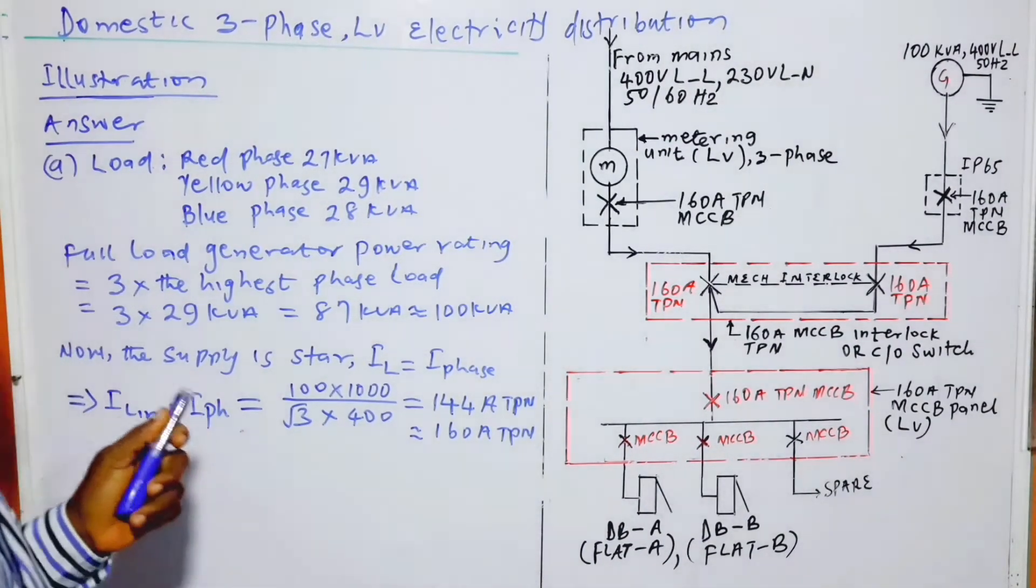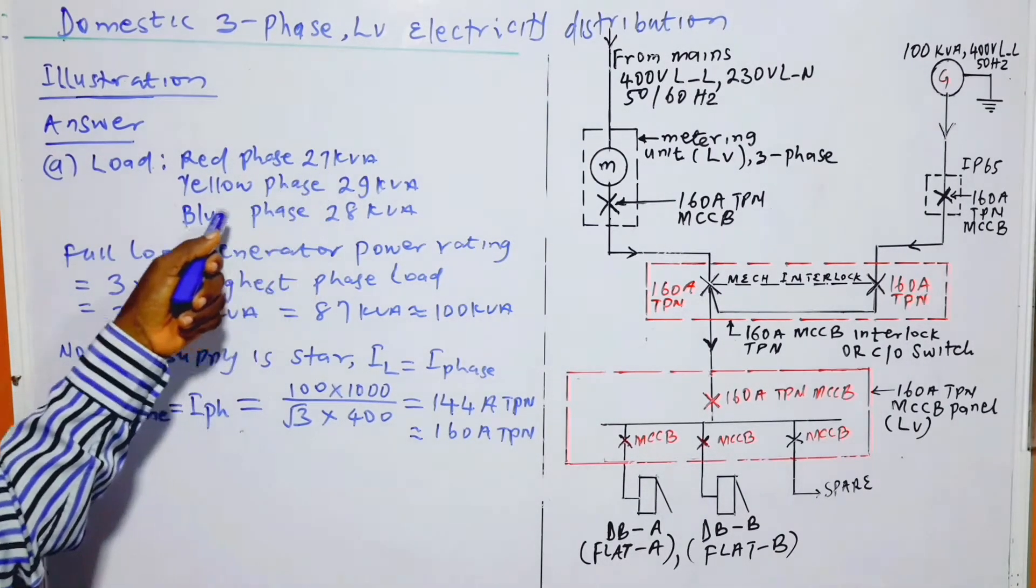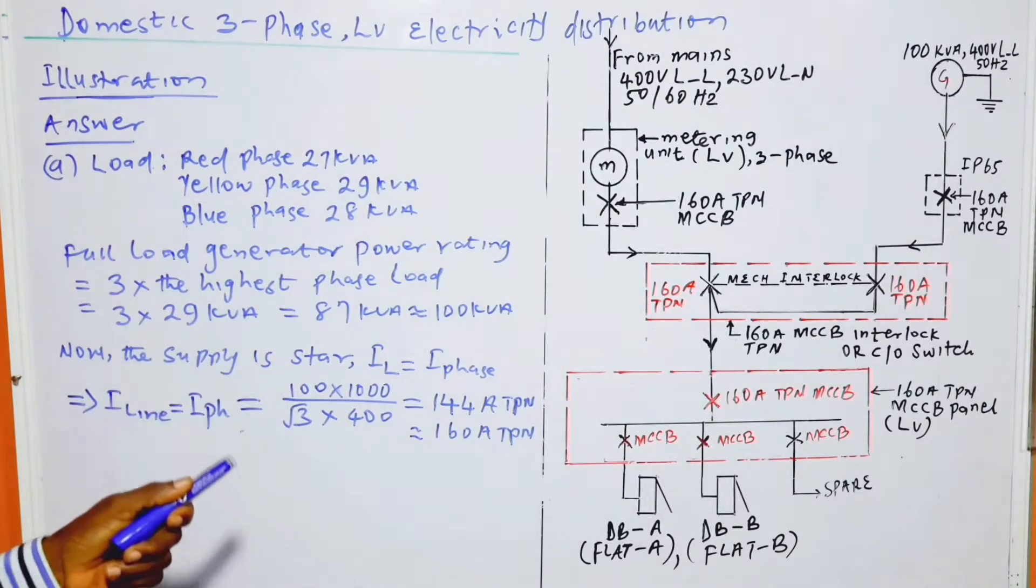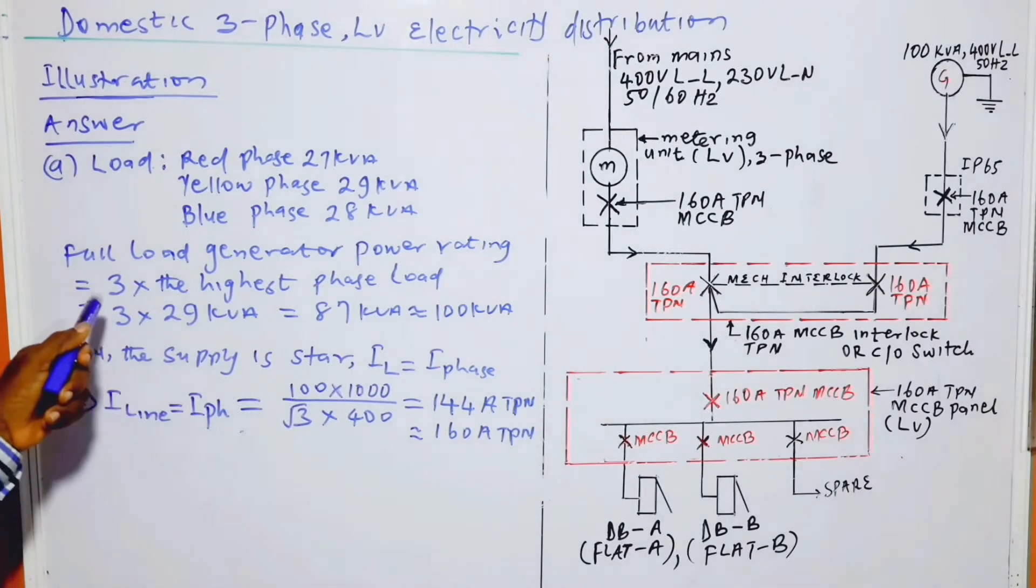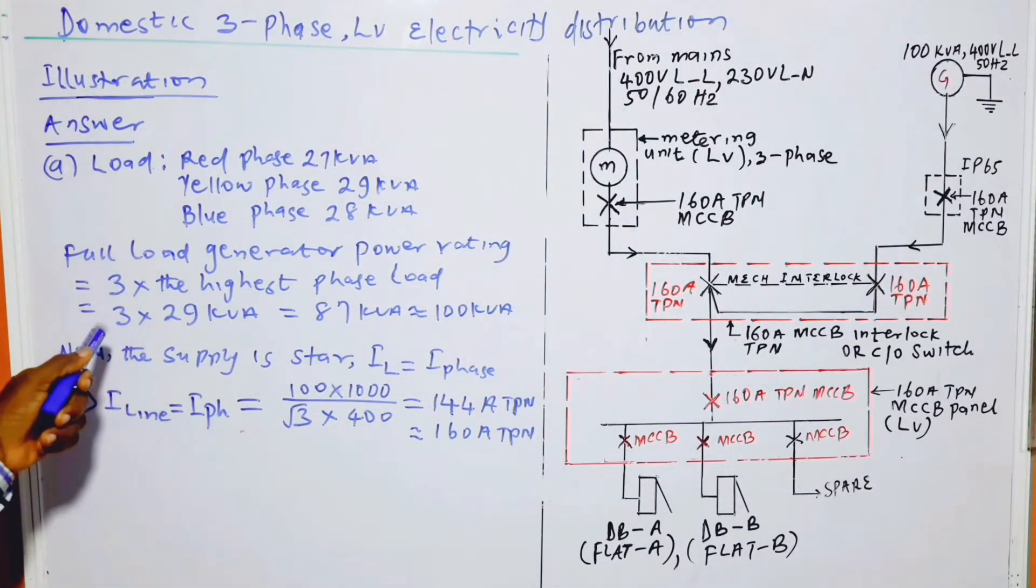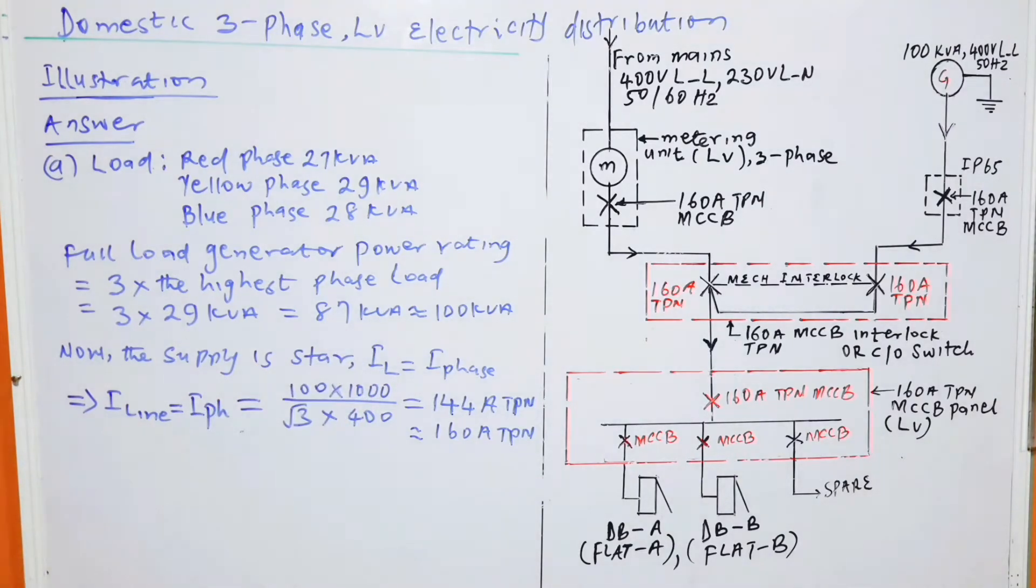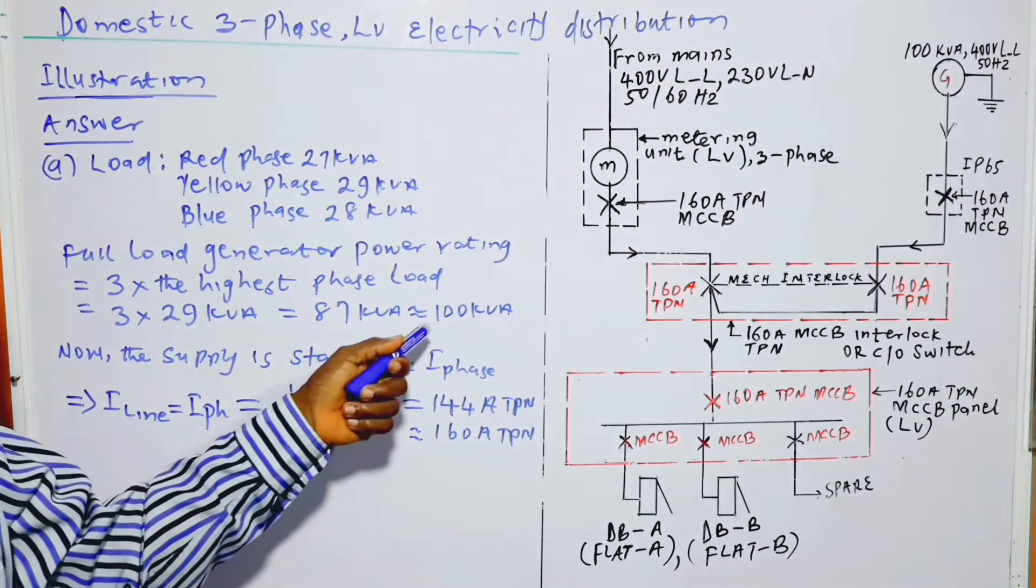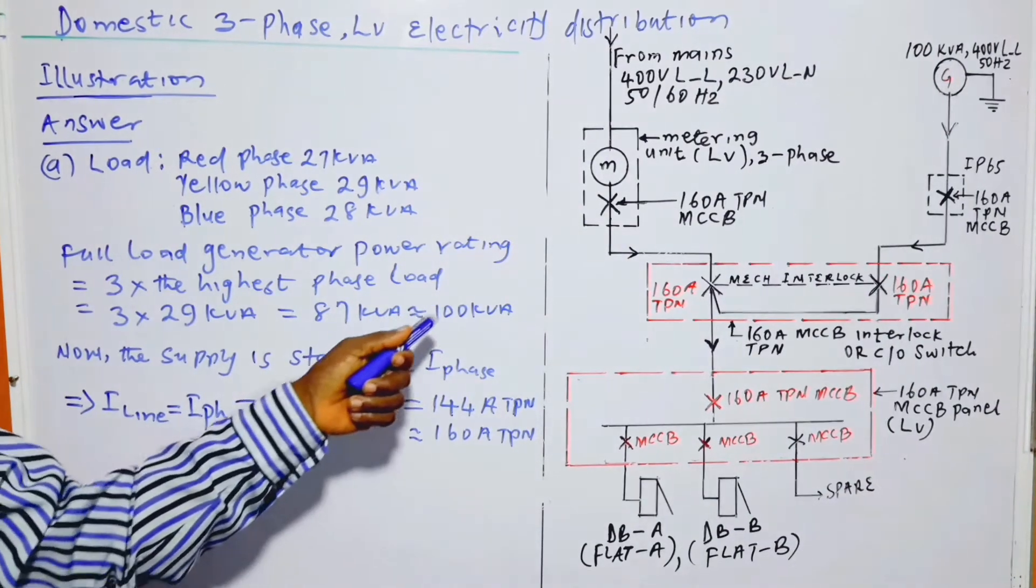Answer to the questions. You have red phase load 27 kVA, yellow phase 29 kVA, blue phase 28 kVA. Full load generator power rating is equal to 3 times the highest phase load, which is 3 times 29 kVA, which equals 87 kVA. The next available generator power rating in the market is 100 kVA, so we choose 100 kVA.